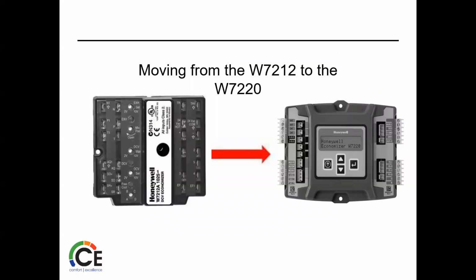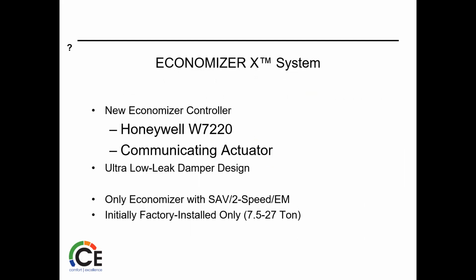All right. So the 7212 is on the left here. That's the old version. The 7220 is the newest version from Honeywell. It's a communicating system, so it uses an actuator that it actually communicates with. It's not just sending a signal to it. You get them on ultra low leak damper designs. Definitely have to have a standard air volume 2-speed electric motor, electric communicated motor. Again, that's a 7220 control on the Economizer X.